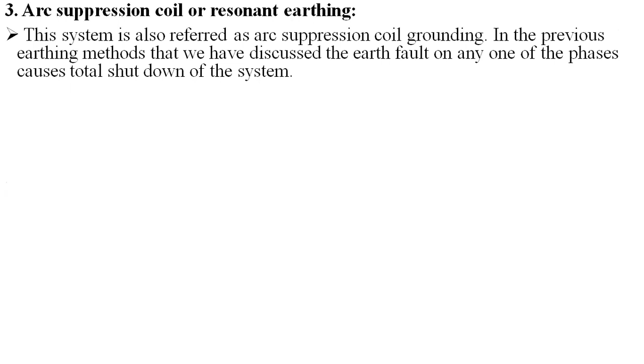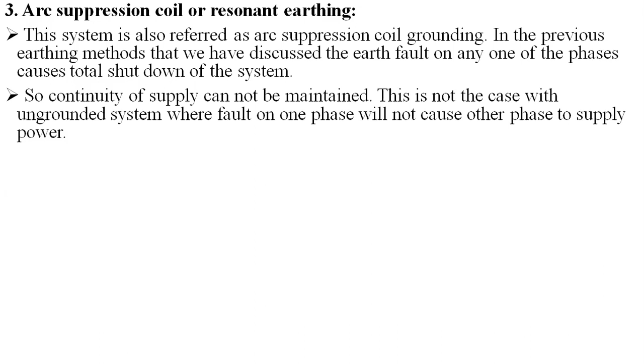Arc suppression coil or resonant earthing. This system is also referred to as arc suppression coil grounding. In the previous earthing methods that we have discussed, an earth fault on any one of the phases causes a total shutdown of the system, so continuity of supply cannot be maintained. This is not the case with this ungrounded system, where a fault on one phase will not stop the other phases from supplying power. So this method of grounding has the advantage of the isolated neutral system along with a reduced possibility of arcing grounds. Numerous other advantages are also there for this system.